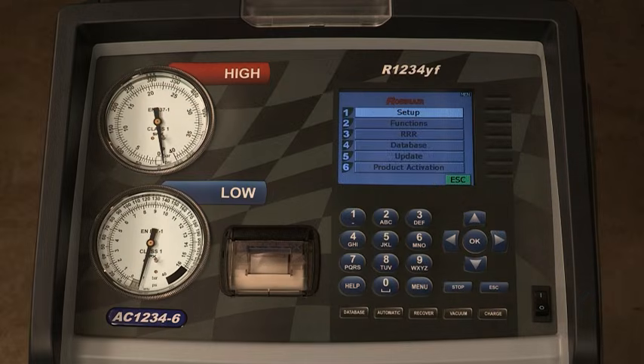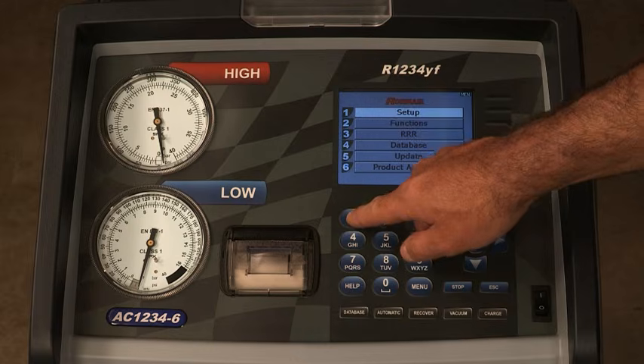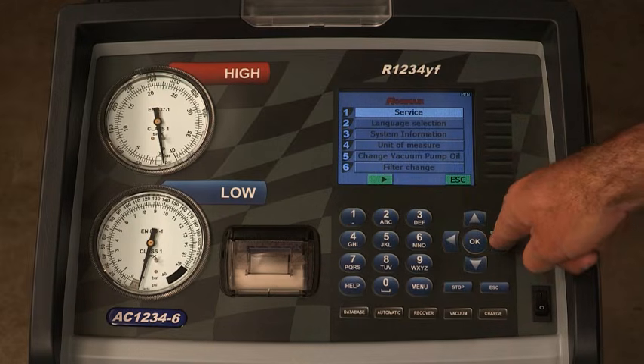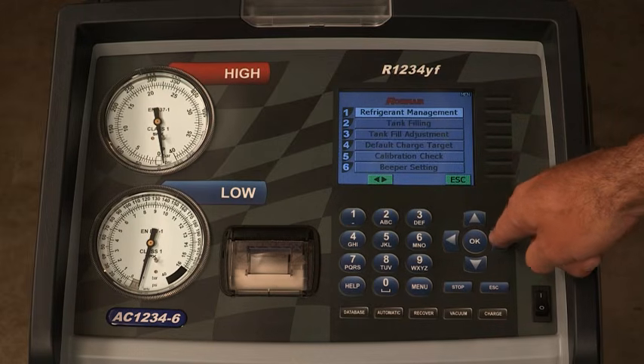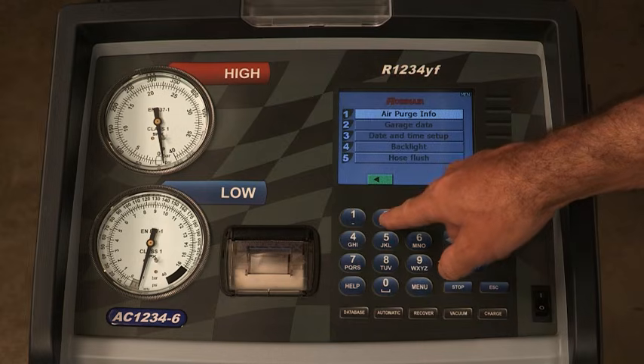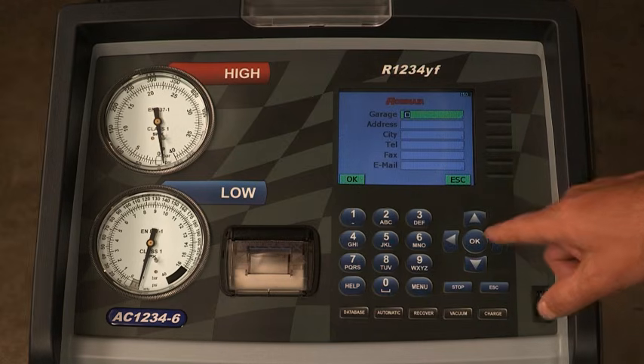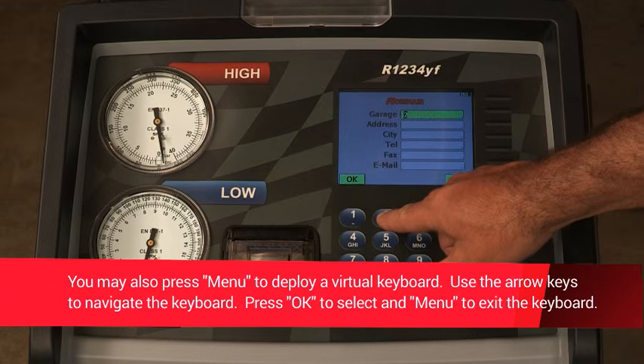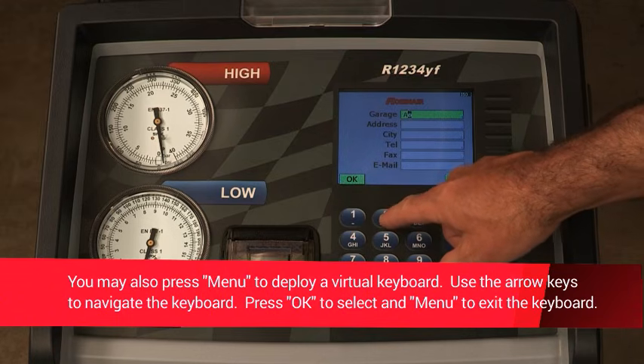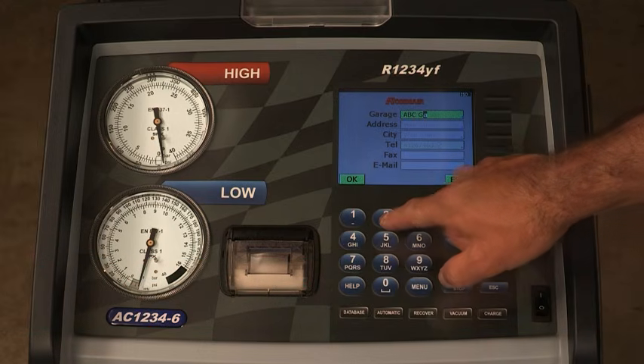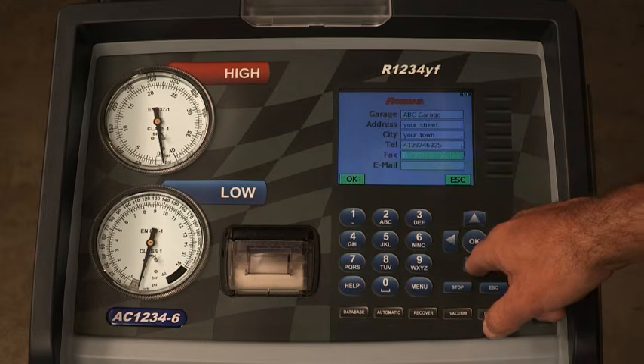This machine has the capability to print out recovery, vacuum, charge and flush information for each vehicle tested. Press Menu, select Setup, and press the right arrow twice until garage data appears. The cursor will blink in the first fill field. Use the arrow keys on the machine's keypad to move around the keyboard. Press OK to enter a character.